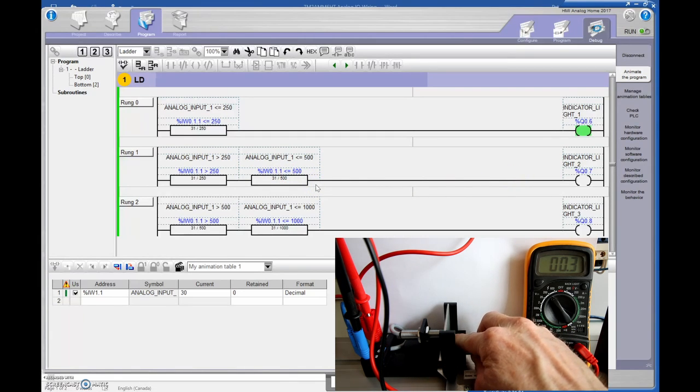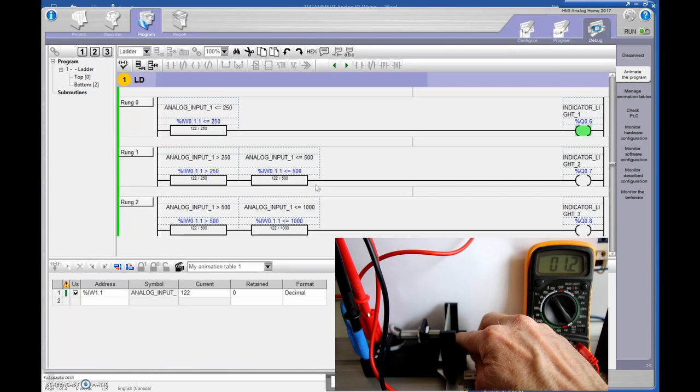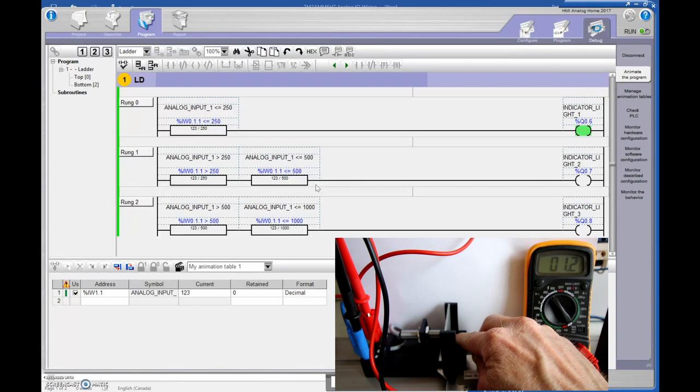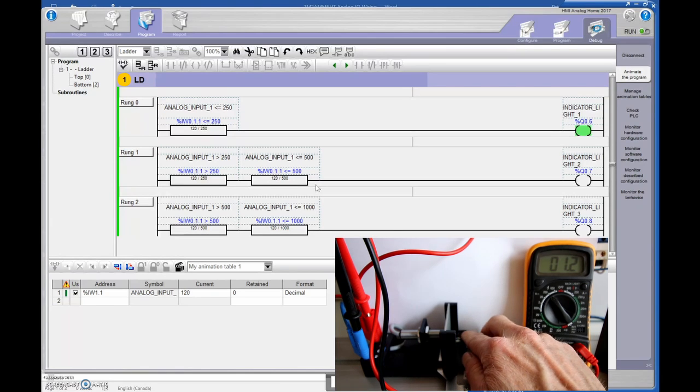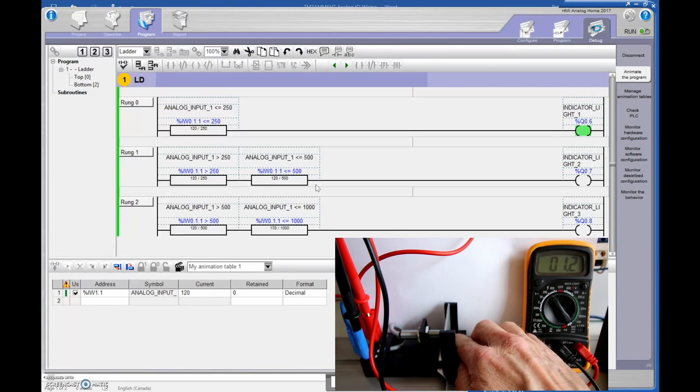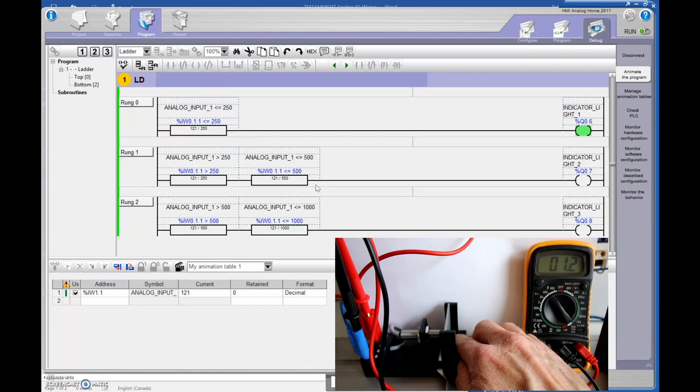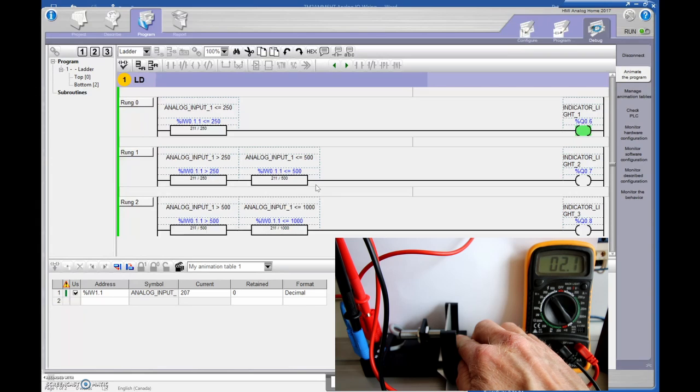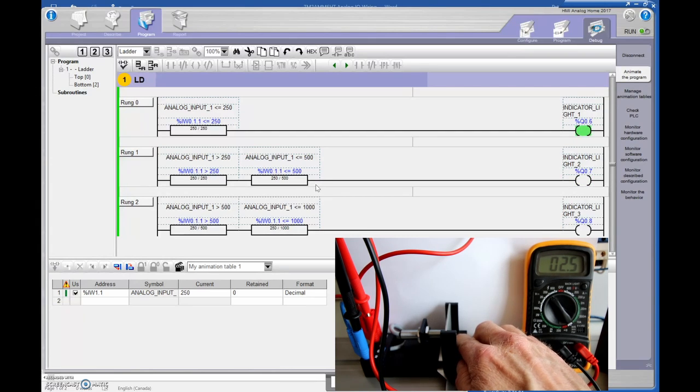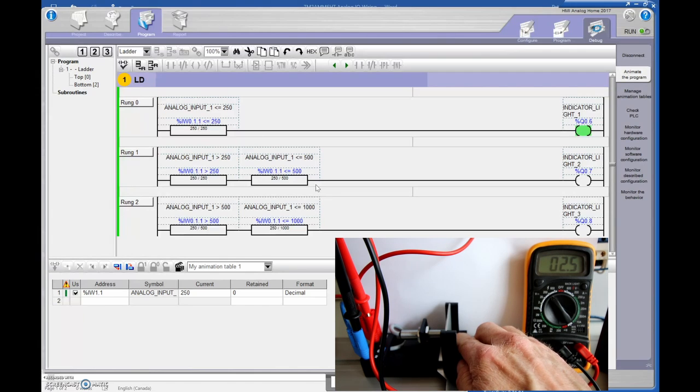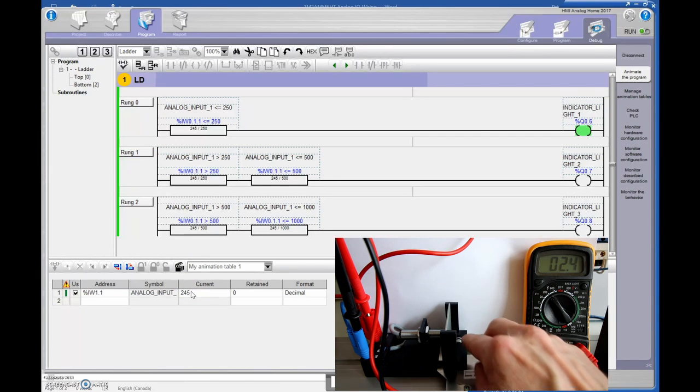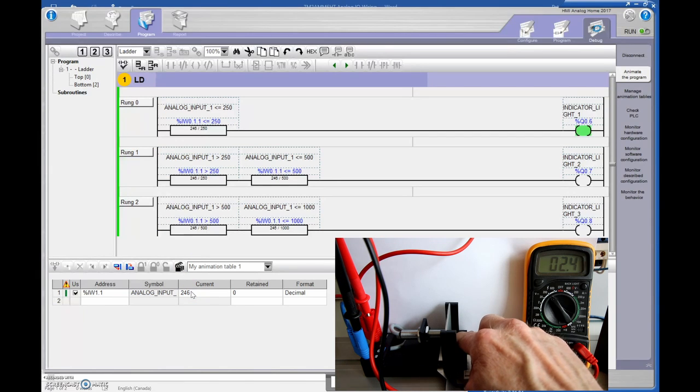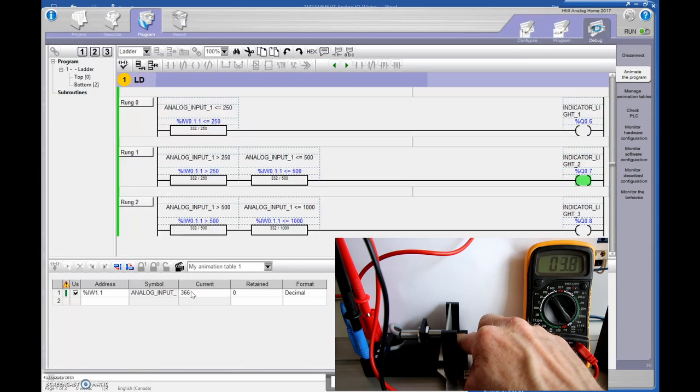And we'll see that this value goes up. This value will be mimicked on every one of my inputs here because they're all looking at the exact same word here on my analog card. And when it gets to greater than two and a half volts, but less than five volts, then the second light is going to turn on. So as I move this, you can see that the voltage is slowly increasing right there. I have 1.2. The resolution on my meter is a little less than actually on the PLC there. So I got 1.2 volts, 1.2 on the PLC. Then I'm increasing to 2, 2.3, 2.4, 2.5. And at 2.5, I'm equal. I can't believe I actually stopped at that value. So it's equal. So the first light is still on. So you can see that this value right here and my meter are mimicking each other. I'm now going to go above two and a half volts and the second light is going to turn on. Beautiful.